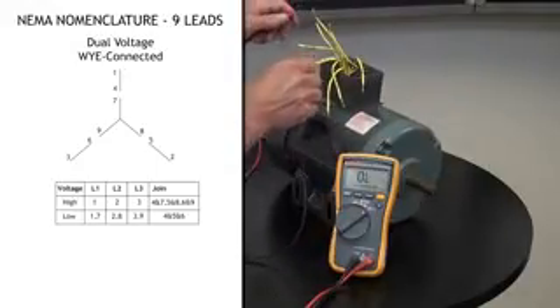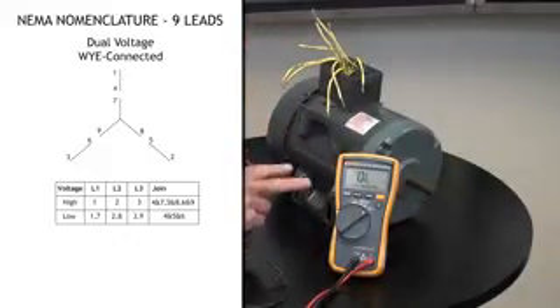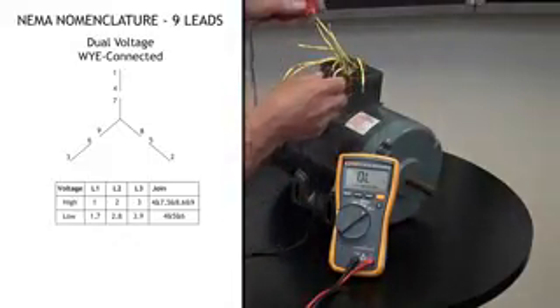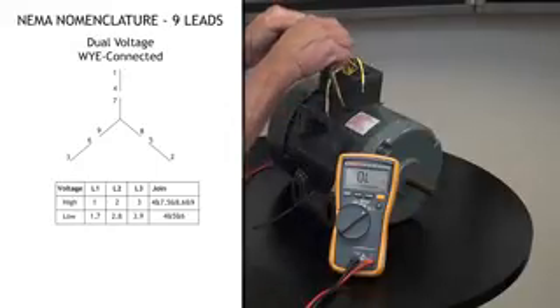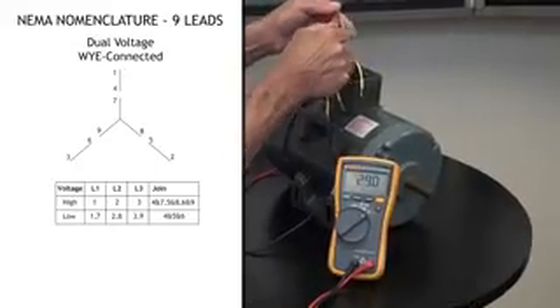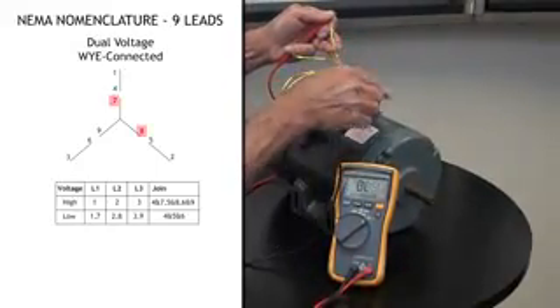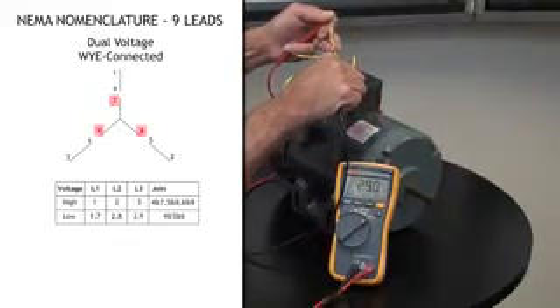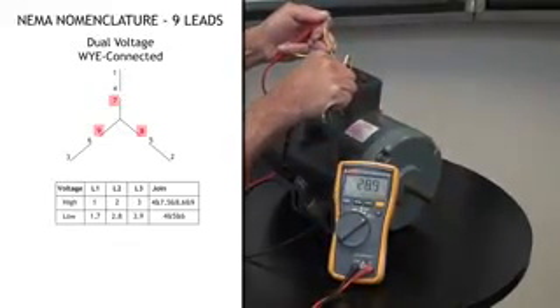This will be a Y connected motor because we've just got combinations of 2, and we can tell that for sure because our Y is going to be our internal connection. We're going to have continuity between 7, 8, and 9. So we know this is going to be a Y configured motor.